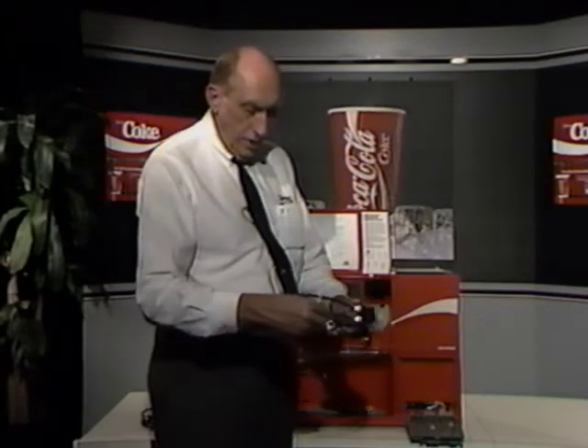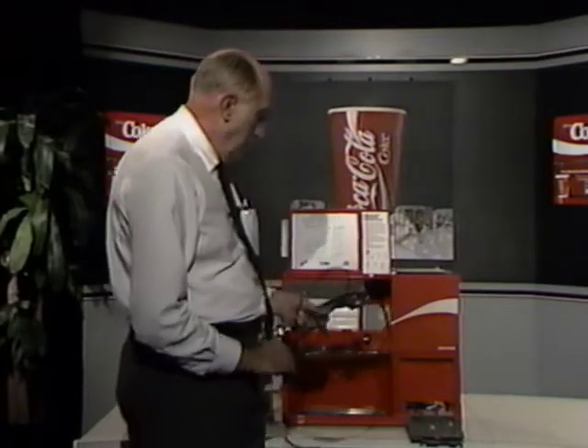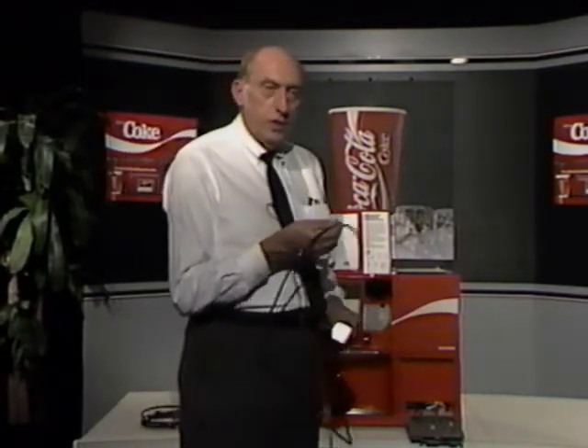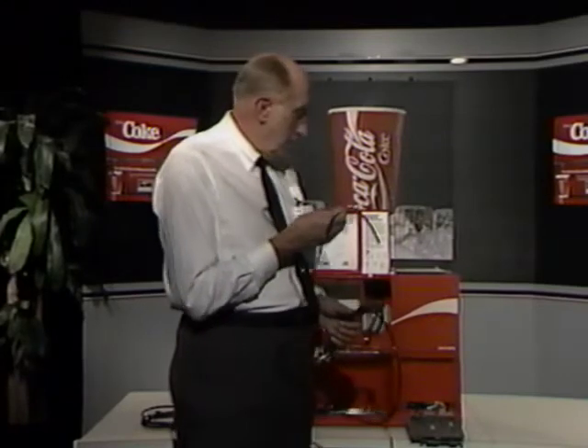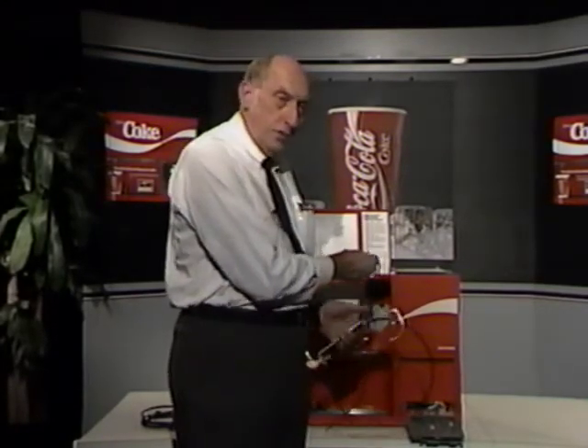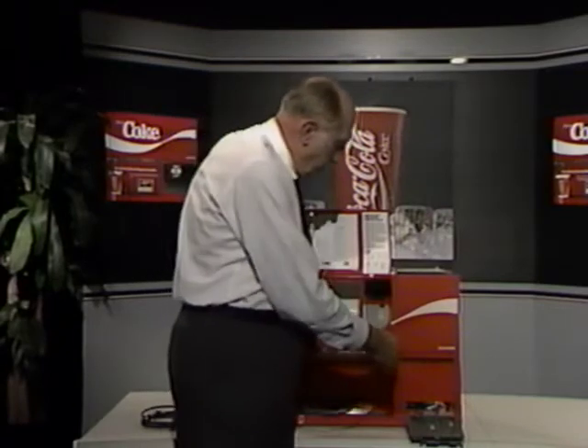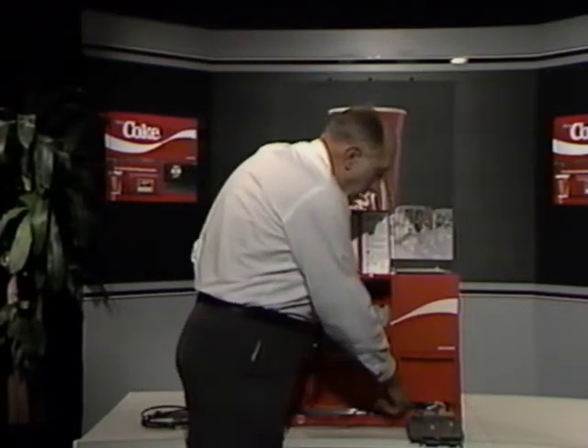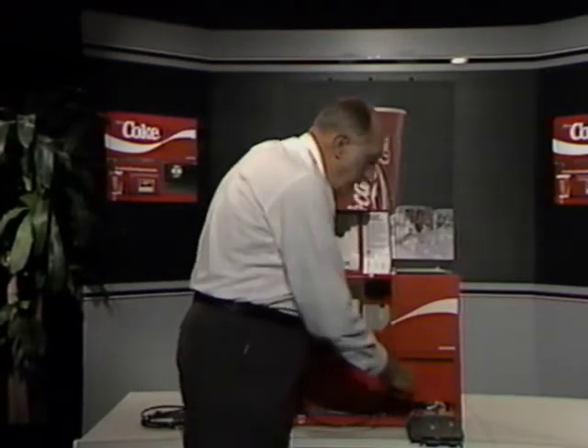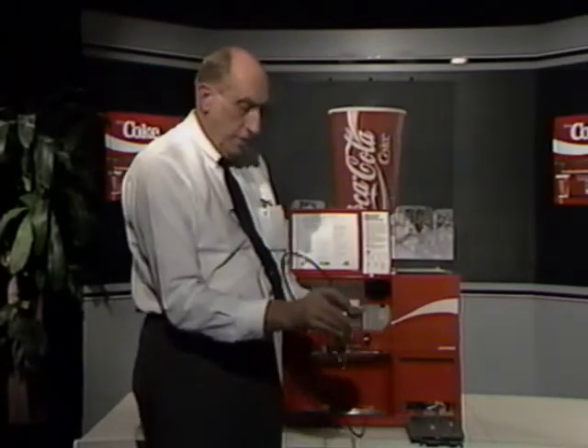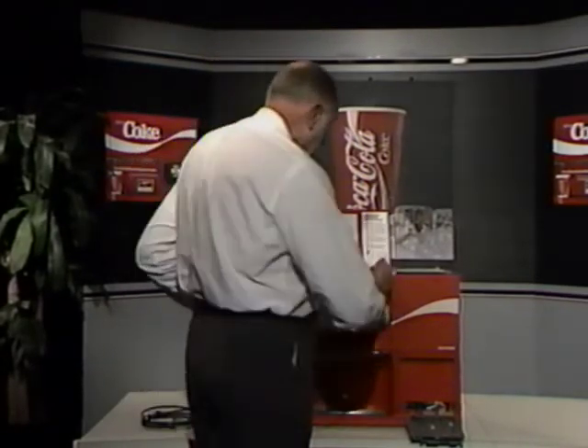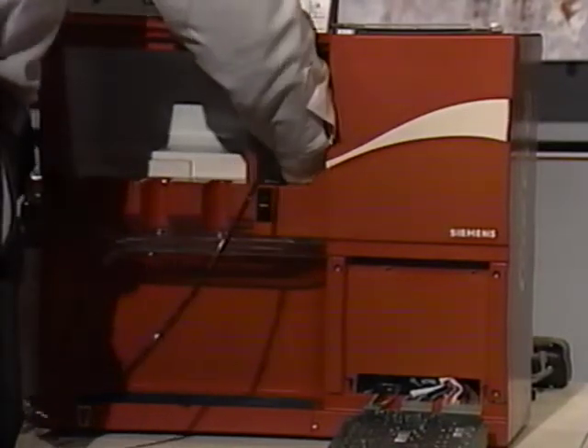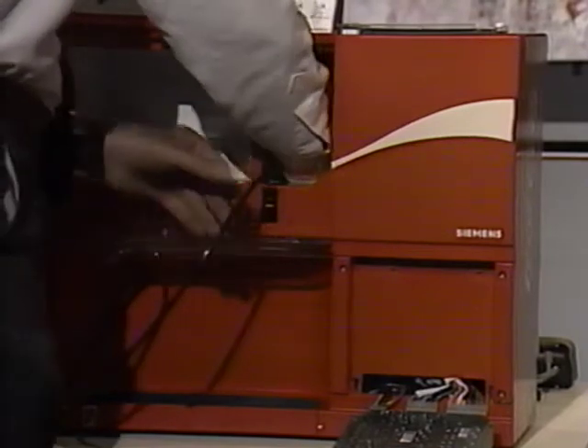The ability to install this kit depends on the fact that we have an outlet opening in the bottom of the CO2 well. And what we're going to do is to install the tubing for the bracket down through the opening in the bottom of the CO2 well that faces towards the front of the machine, and it will come out this opening just below the ECM board. Then we're going to pull it through. The hose is installed simply by pushing it through the opening.